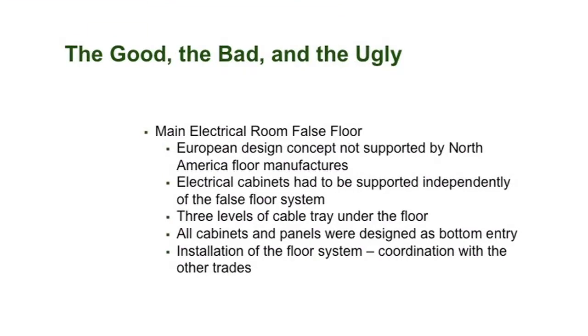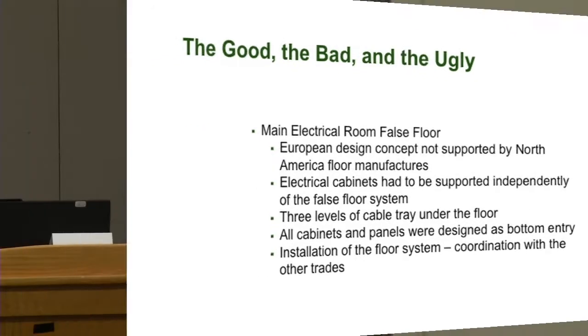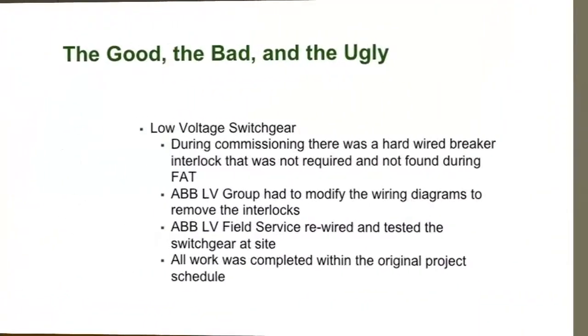So our solution was we built independent equipment frames out of Unistrut, anchored them to the concrete floor, and then built the floor system around the equipment frames. But once the equipment is set, it becomes a flawless system. You can't see the Unistrut frames, you just see the floor tile butting to the equipment door. This gives you total access underneath the floor, and has a nice finish to it. But also to implement this, we ended up putting 3 levels of cable tray under a 39-inch floor. So basically, it was a challenge that we were able to overcome to meet the requirement of the project.